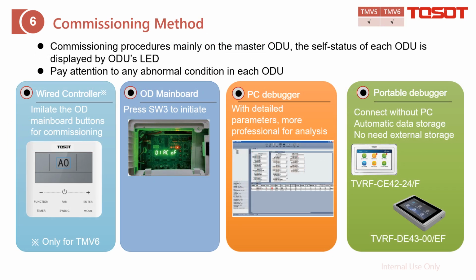Commissioning method. There are 4 ways. First is the portable debugger. You can connect to the indoor unit or outdoor unit. Currently, we have 2 models. CE42 is the second generation and DE43 is the third generation. You can also do the commissioning from the PC debugger, this one, or you can do this from the outdoor unit PCB. And only for TMV6, you can do this commissioning from the wired controller because we make the wired controller imitate the outdoor unit main board buttons.